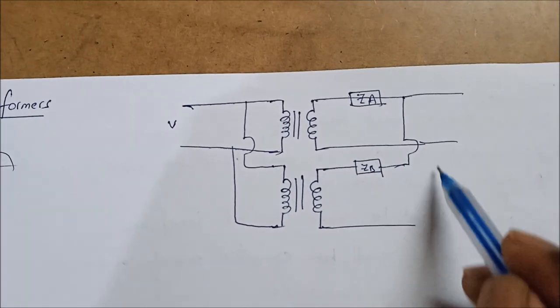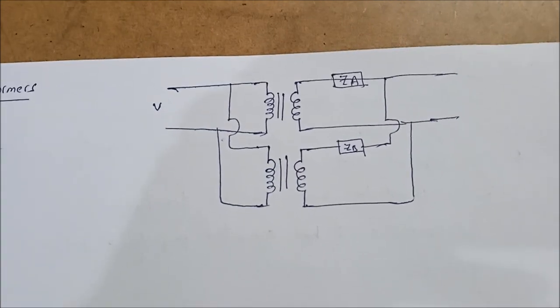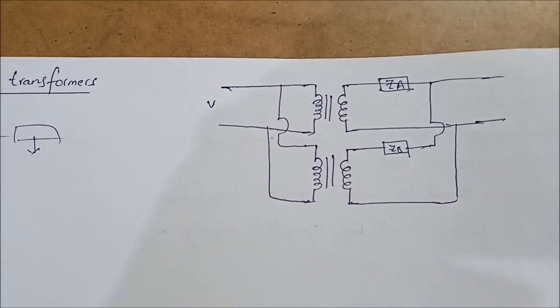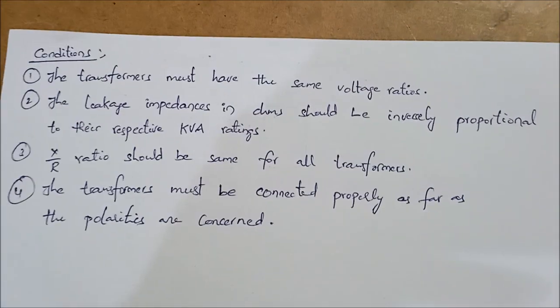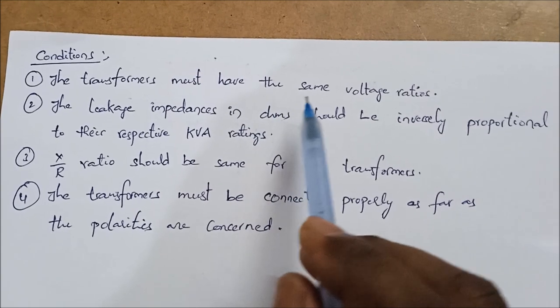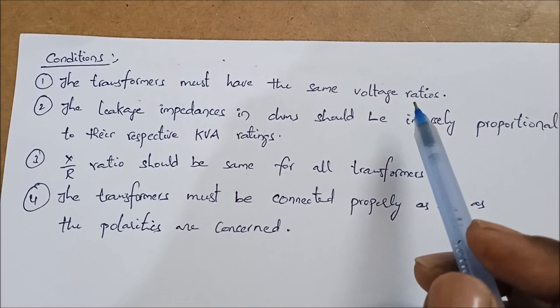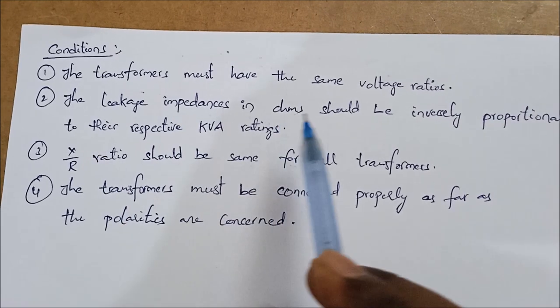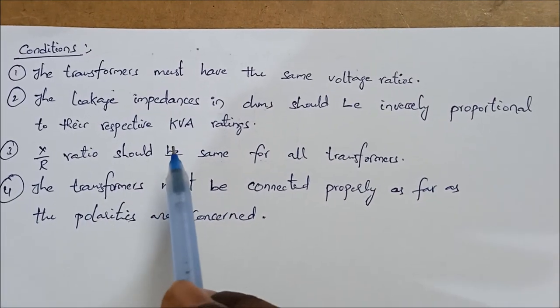If you want to connect two transformers in parallel, there are some conditions which must be satisfied. The first condition is that the transformers must have the same voltage ratios — that means if you give the same input voltage, the output voltage of all transformers should be the same. The second condition is that the leakage impedance in ohms should be inversely proportional with respect to their KVA ratings.